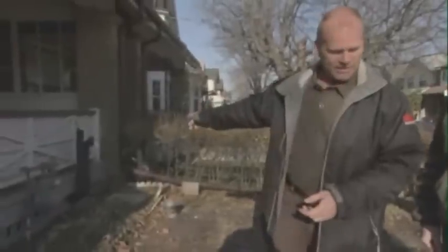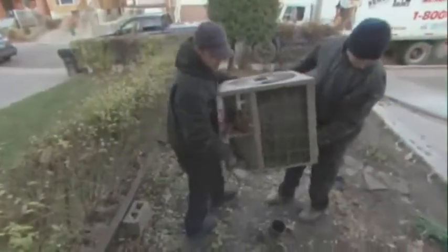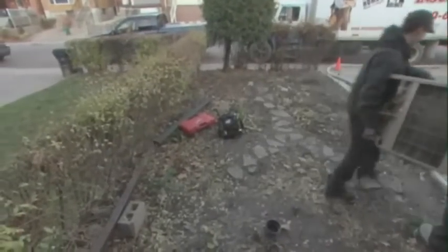We had an issue, and I talked about this, the air conditioning sitting in place right by the venting, so the exhaust from the furnace as well as the intake being right over top of the air conditioner, unacceptable. So what we've done, because you need a new air conditioner, right? We've disconnected it. Oh. So we've now made it legal. You're going to have to find another location for it when you put in your new one. Right. Let's go around the back.